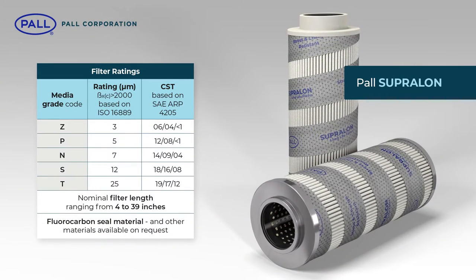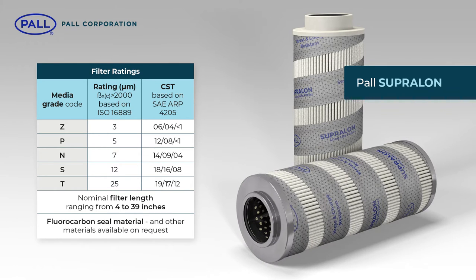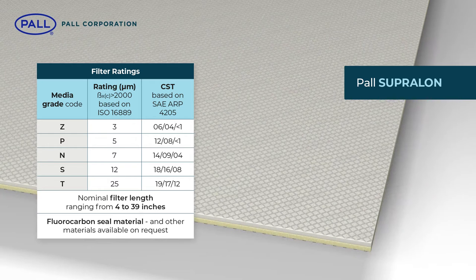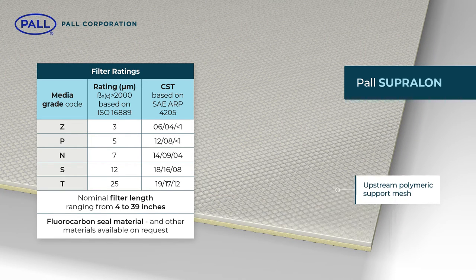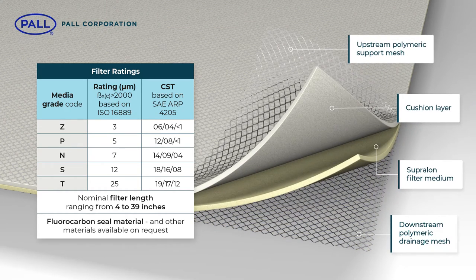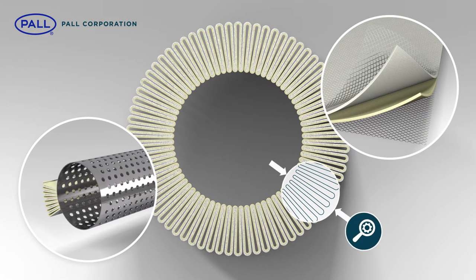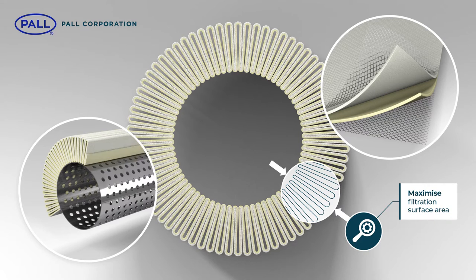Supralon filters come in a range of sizes, ratings and core configurations to fit existing Pall Ultipore and some alternative makes of filter housing. The filter media pack consists of an upstream polymeric support mesh, a cushion layer, the filter medium itself and finally a downstream polymeric drainage mesh. Supralon's stress-resistant depth filter media consists of a highly porous, tapered pore structure that enables the coarser upstream surface to act as a pre-filter, capturing larger particles while allowing finer downstream pores to trap smaller particles. The media pack is pleated and the pleat height and count are optimized to maximize the filtration surface area.